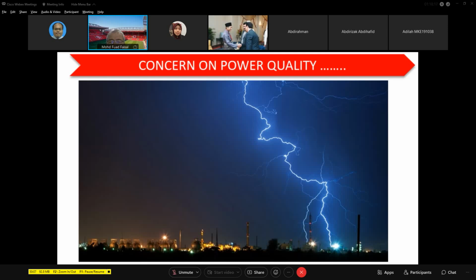Okay, when this kind of scenario happens, especially lightning, it will strike the power line. As we know, lightning can damage our astro recorder, computers, telephone, etc. It causes the voltage to have a transient event. Voltage will increase immediately, and then it affects the equipment, so the customer equipment can be affected. The same goes for TNB. When lightning strikes a power line, despite having a lightning protection system like tower footing resistance and earth wire, it will cause the voltage to fluctuate, so we have voltage sag. Sometimes we have information from TNB saying that the cause of the voltage sag was lightning. So it's true. This is due to back flashover.